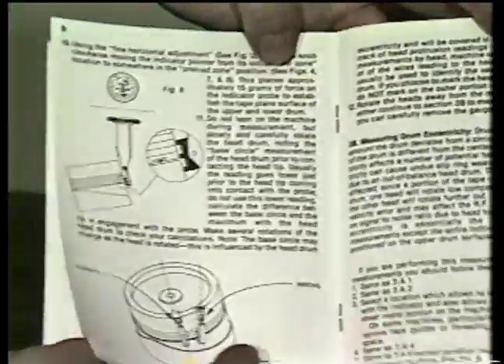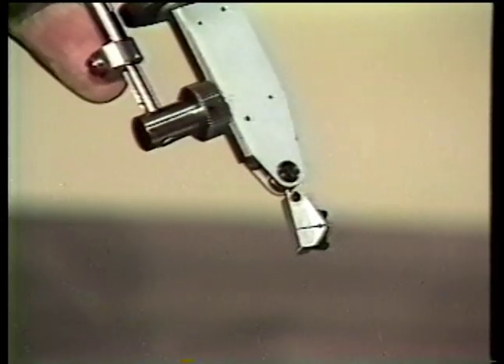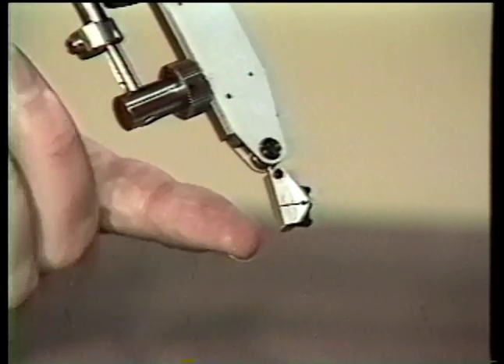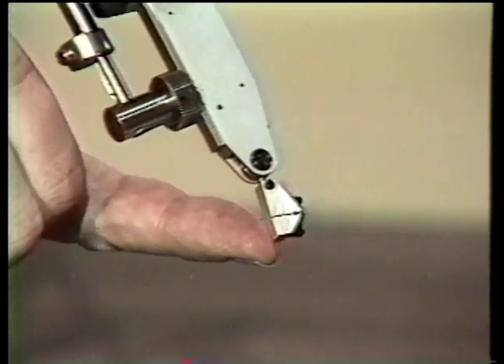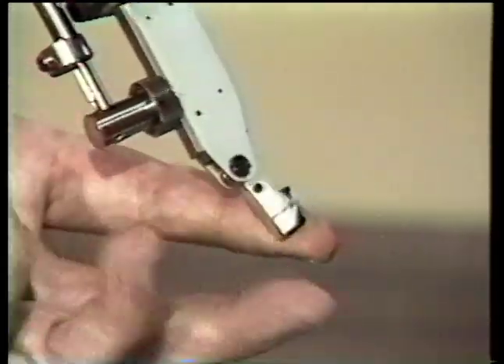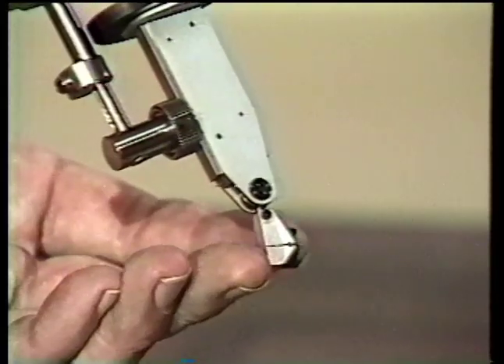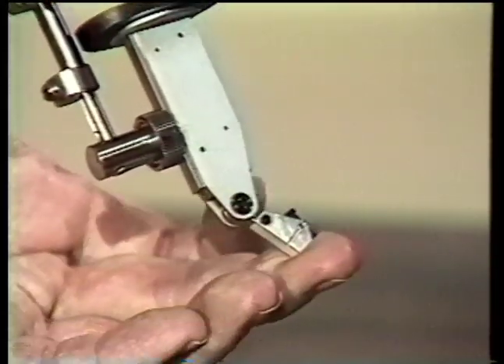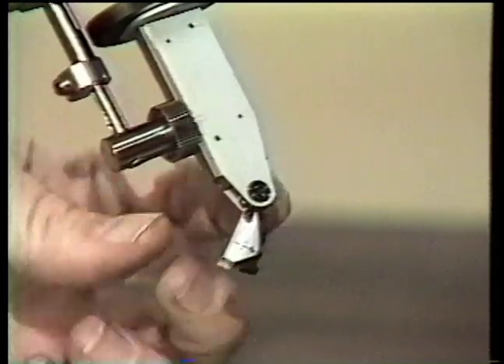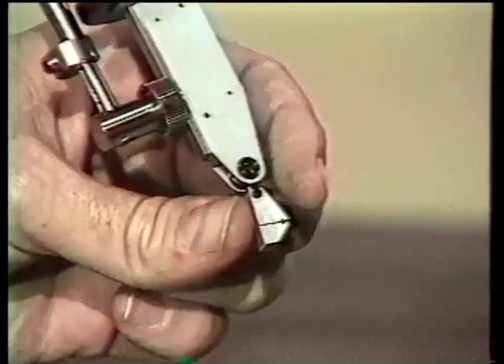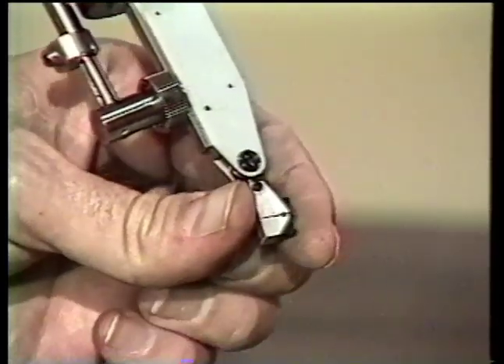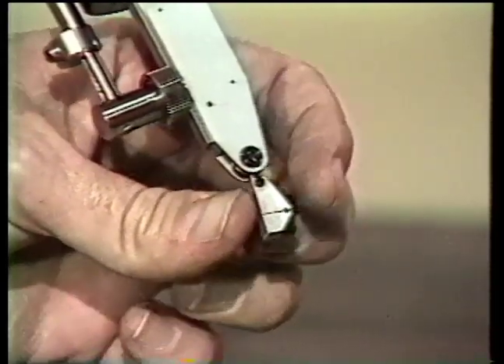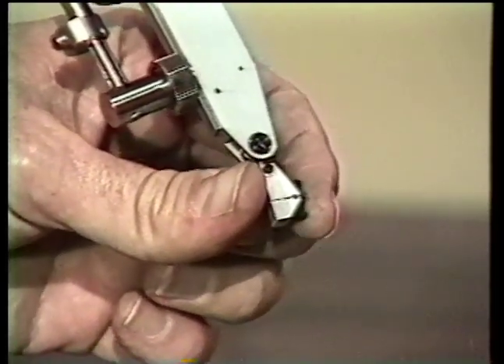The entire setup procedure and parts positioning and so on is explained in this booklet. This is a close-up of the HPG-1 foot. You notice that the whole shoe assembly, the aluminum portion, is actually mounted on a slip clutch. The reason for this is that we want this little shoe, the black plastic part, to be self-aligned to the drum surface. However, it can only self-align to about ±5 degrees.